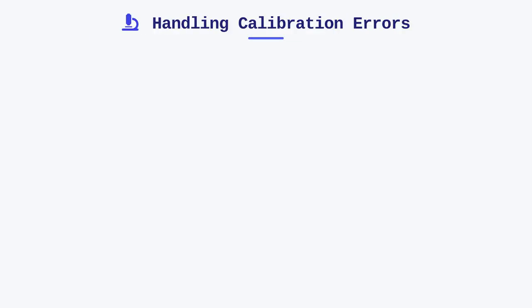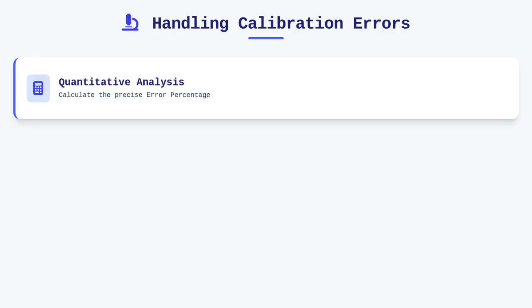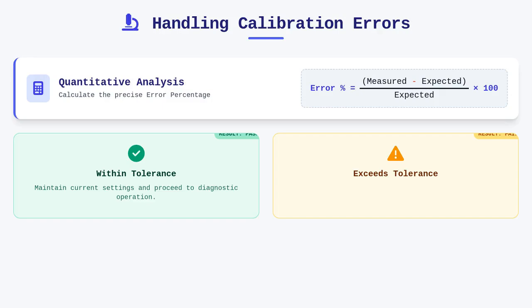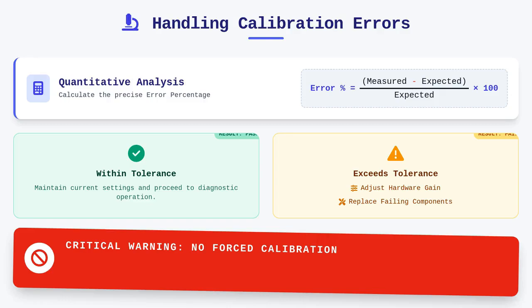When we encounter calibration errors, we move beyond simple adjustment and into the realm of quantitative analysis. Calculating the error percentage is a straightforward yet critical step involving the subtraction of the expected value from the measured value, divided by the expected value, and then multiplied by 100. If this percentage exceeds the tolerance limit, you must adjust the hardware gain settings or potentially replace failing components if the drift persists. Never attempt to force a passing calibration by ignoring repeated failures.